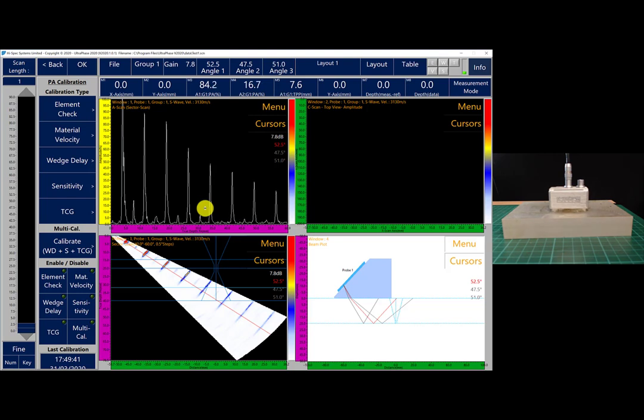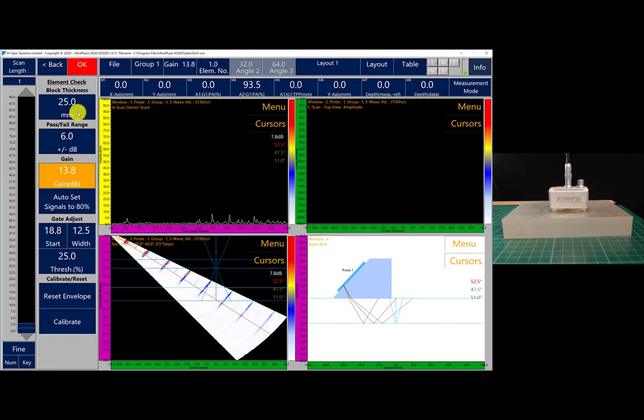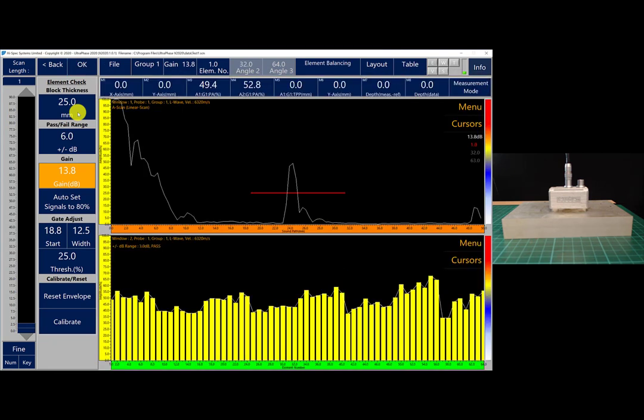Let's go into the element check calibration menu. Step one would be to set the block thickness. Our block is at 25mm.